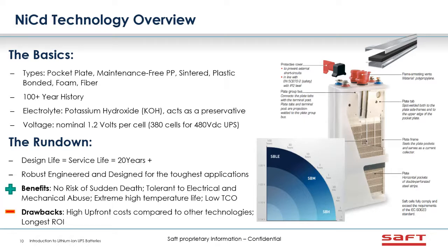The rundown here is that the design life equals the service life, and it's over 20 years. I've seen some NiCads still in service that have been 35 years going. They're very robust. They're designed for the toughest applications. If you look at the picture on the right here, it's kind of hard to see, but that metal structure is actually a steel that's perforated to allow the electrolyte to seep into the active material to be part of the chemical equation. So there's a very rigid structure holding the active material inside. It doesn't get out of those pockets, and so that alludes to the robustness and the tough applications that we can handle with this technology.